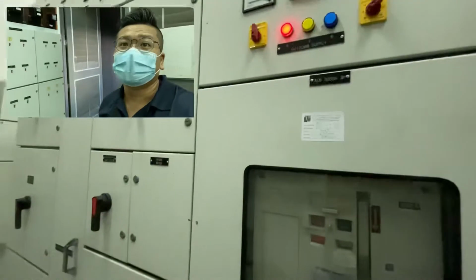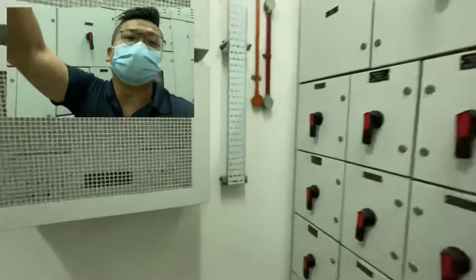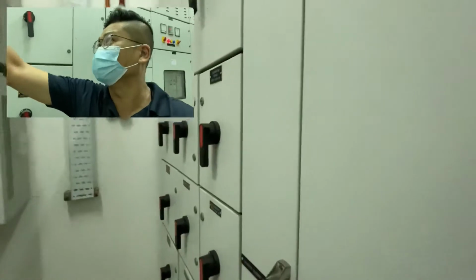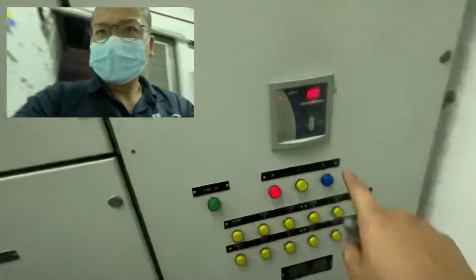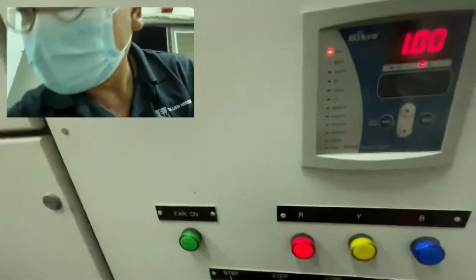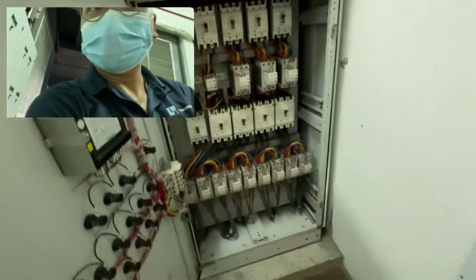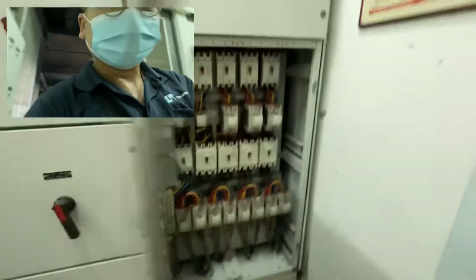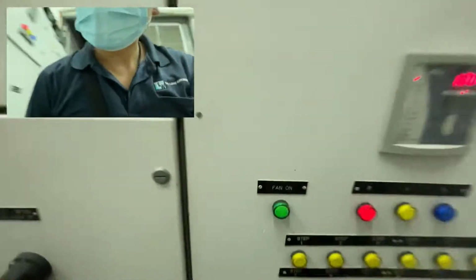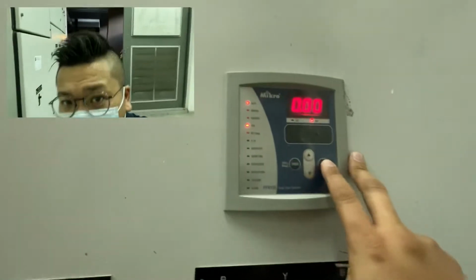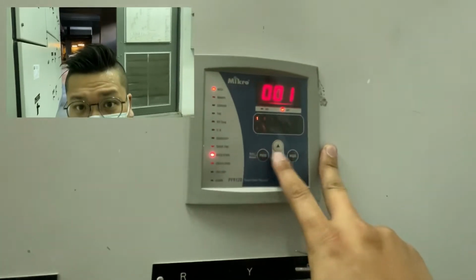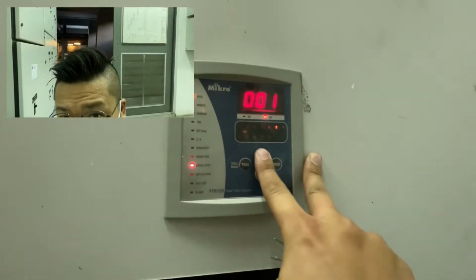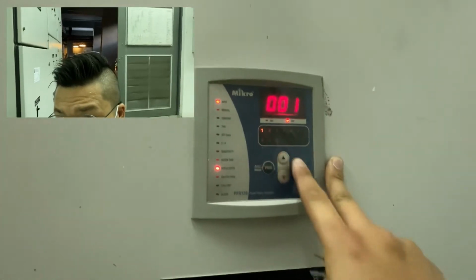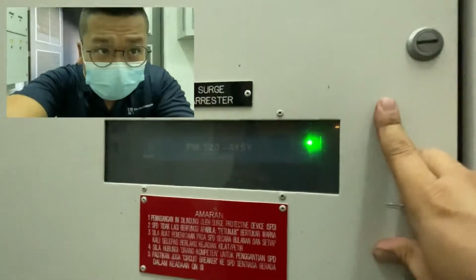Okay, here we are. This is the MSB number 2. So I start the genset from MSB number 2. This is a capacitor bank. Currently the load is low, that's why there's no step going in. Let's check everything is in good condition. Okay. Let's see, is there any step faulty? Go to rated step, okay? Then browse through all the steps. Okay, in good condition. Surge arrestor. Okay.